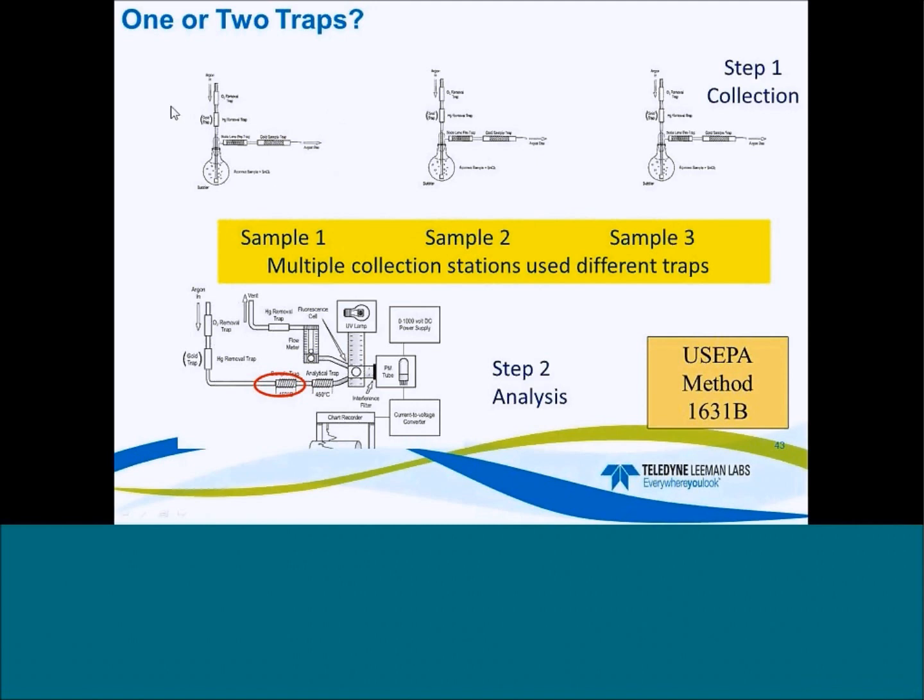First, they would have a collection chamber, which might be in a fume hood and contain 5 or 10 of these stations. Each one, they would load their samples into, load in their stannous chloride, and they would start to bubble through the sample container. It would release the mercury, go through a dryer tube, and collect on a gold trap. And that would be done perhaps in 4, 5, 6 more locations.